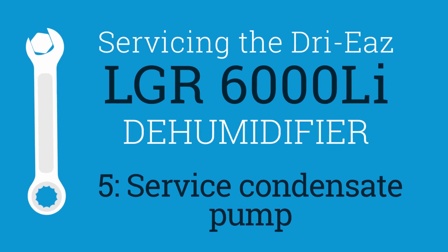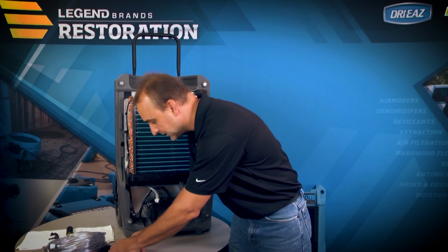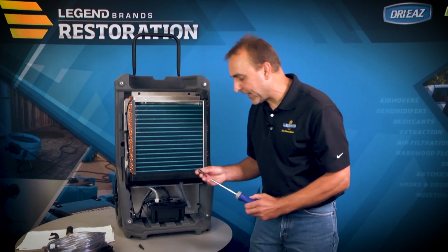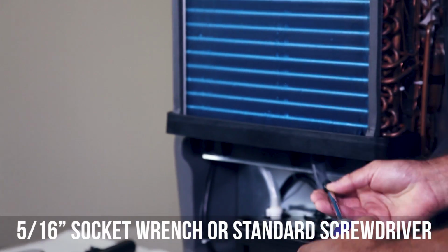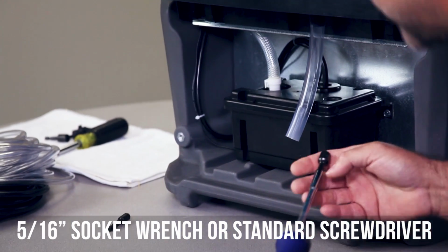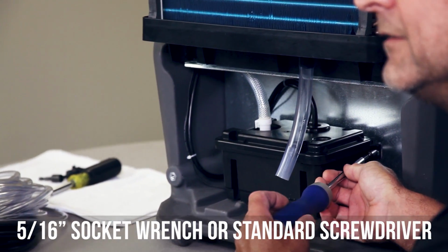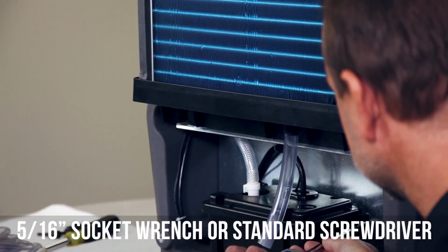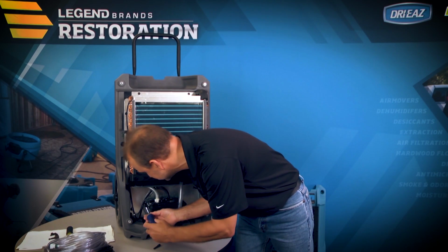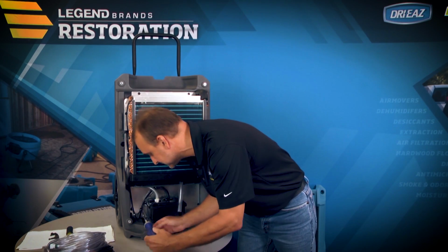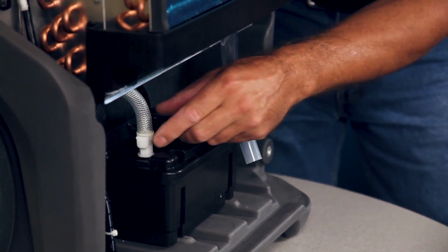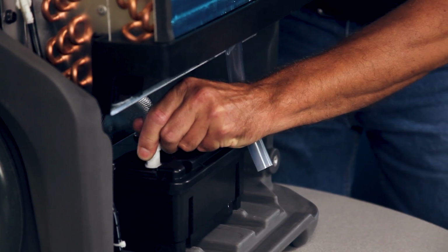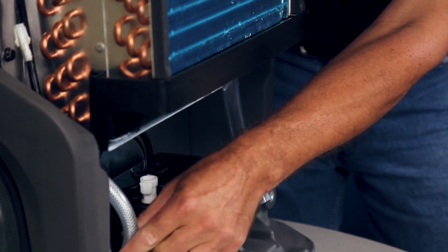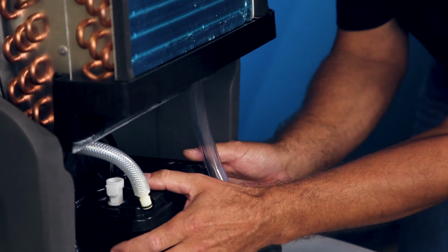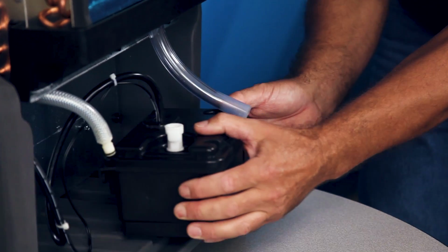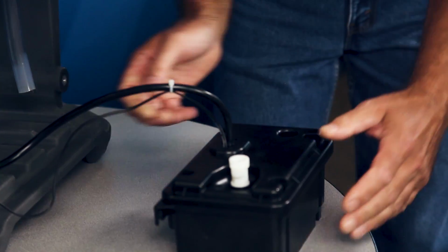To remove the condensate pump from the housing, you just need to loosen 2 5/16 hex head screws. You may also use a standard or flathead screwdriver. Back the screws out a few turns. Grab the condensate pump output line, which has a quick disconnect.